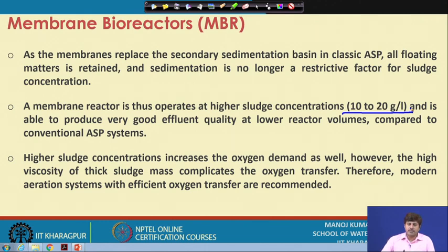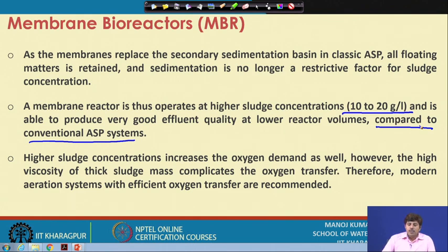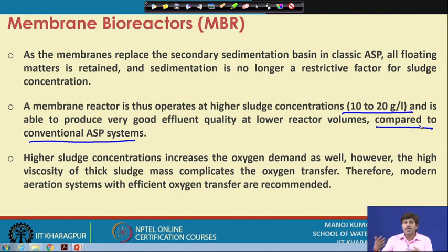When operated at higher sludge concentration, the system produces very good effluent quality even at lower reactor volumes. Performance is actually better than conventional activated sludge systems. Higher sludge concentration is the main reason — if there is a lot of biomass, they will quickly degrade the organic matter present in the system, and the rate of organic matter decomposition will be higher, enabling greater BOD and organic carbon reduction.